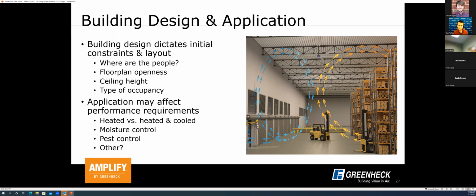Some important things to be aware of here, and some general rules of thumb: I typically recommend that when you're looking at where to place an HVLS fan, focus on where the people in the space are, or where the problem you're trying to address is located. So if you're having condensation on the floor in the back corner of a warehouse, that's where we want to look at installing those fans, with a layout that ensures enough airflow reaches that back corner.